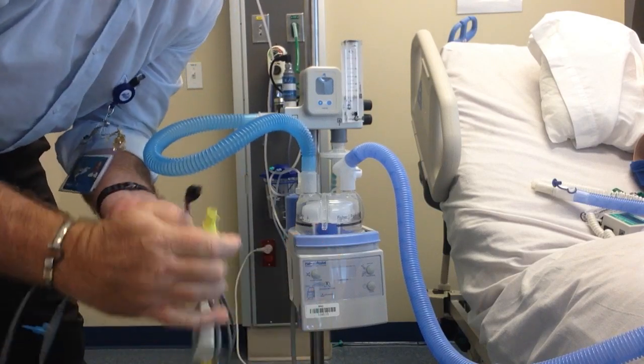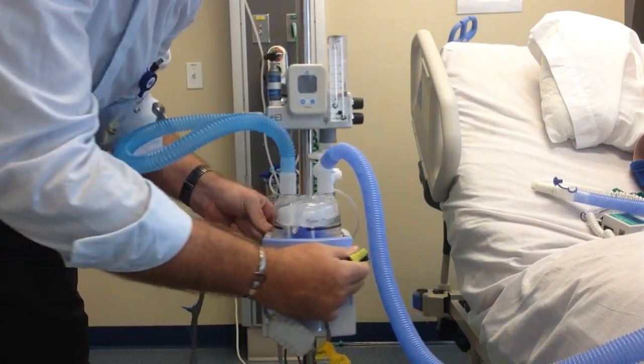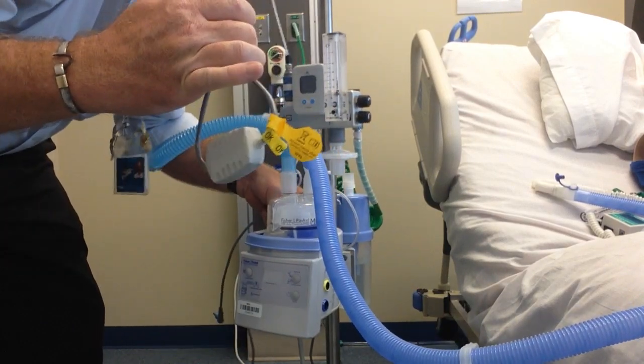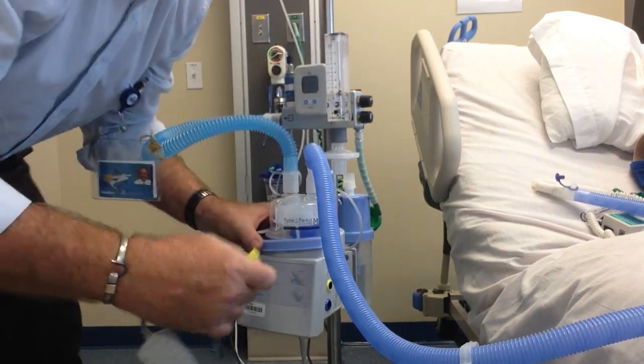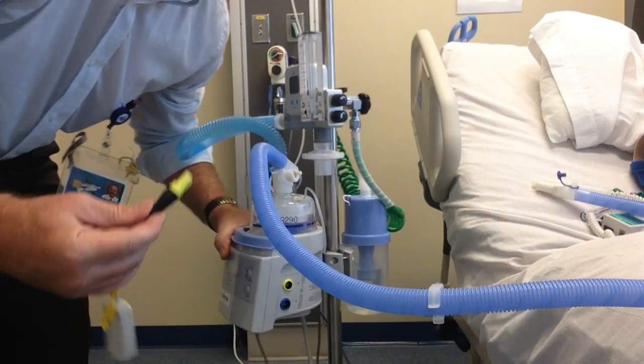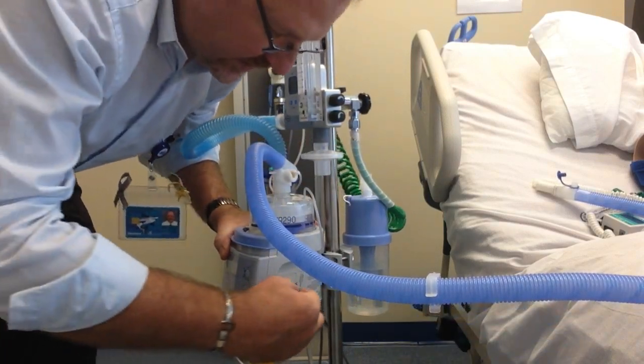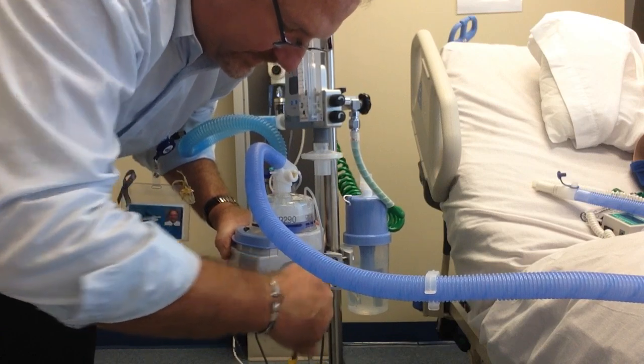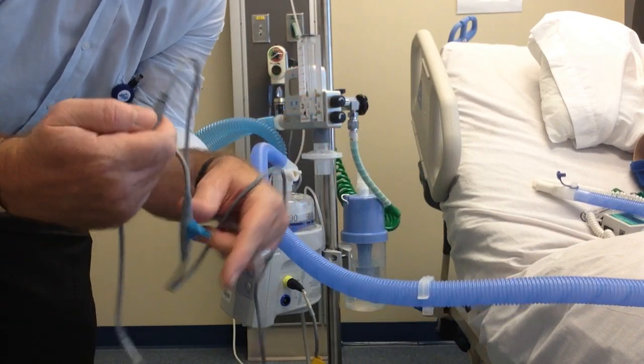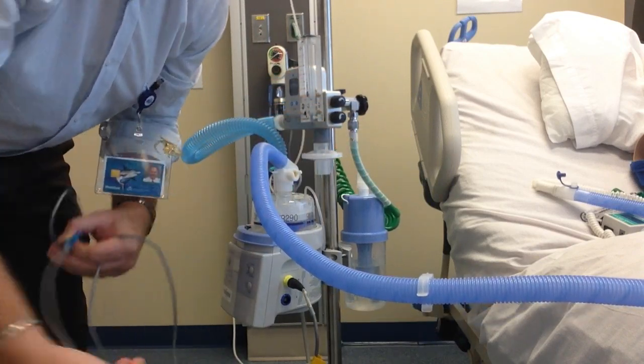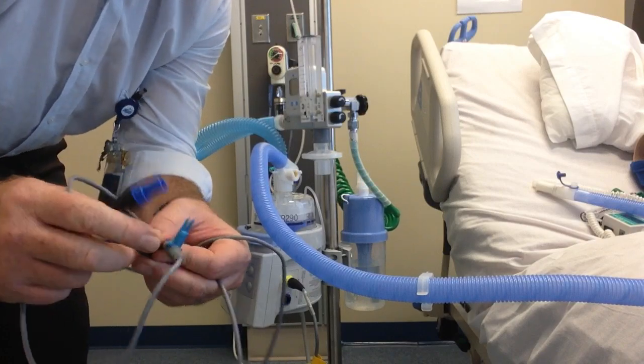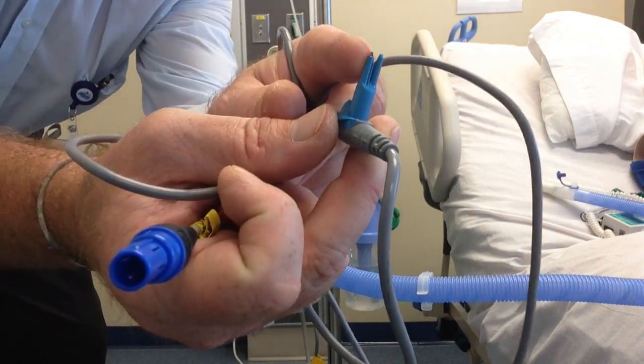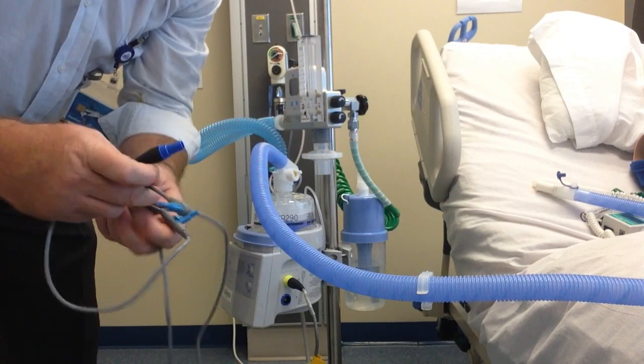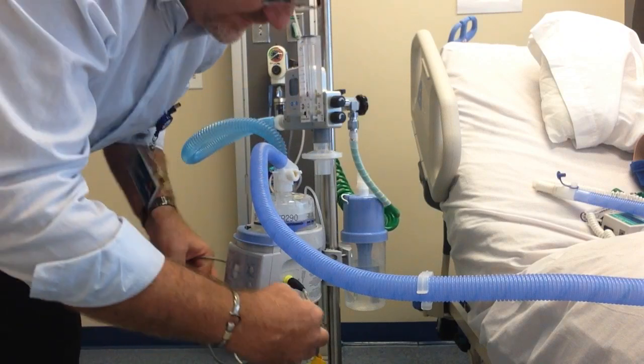Now, when we use this, we have a single pigtail. You can use a double pigtail, but we have a single pigtail here. This supplies the power to the circuit to keep the wires hot. Now, this is the really hard part to hook up. Yellow goes to yellow. These are your temperature probes to monitor your temperatures in your chamber and everywhere. So this one looks like it's broken, but it is not. It's missing some metal. Now this one's also hard to hook up. Blue to blue.